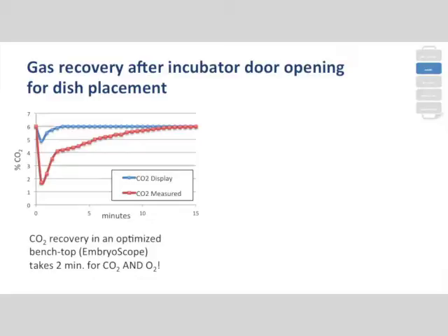Gas recovery, that's my favorite. I mean, we all more or less rely a little bit on what our incubator tells us. That's what the incubator tells you after a door opening. That's the display of the CO2, and you can see that the CO2, according to the incubator, is recovered within 2 to 3 minutes. But if you make an external measurement, it takes much longer. It's about 15 minutes where the CO2 needs to come back to normal. That's a standard-sized incubator. Most of us still use them.